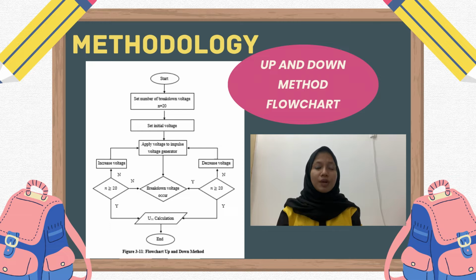When no breakdown voltage occurs, the number of shots is checked to see if it is completed 20 times or not. If insufficient, the voltage will be increased by applying a voltage gain. If the number of shots reaches 20, the next step is to compute the 50% breakdown voltage, U50.